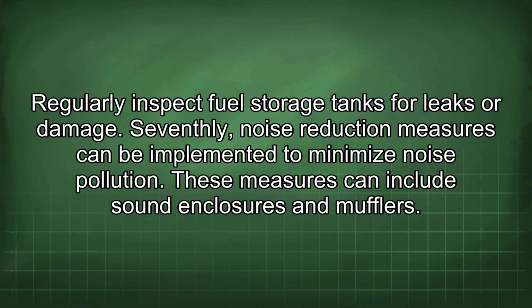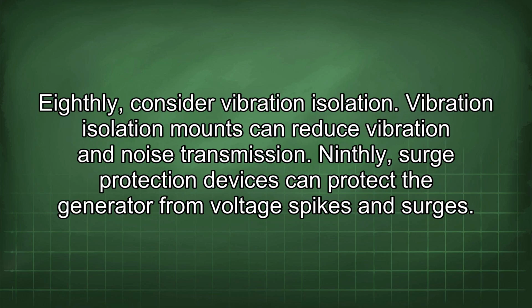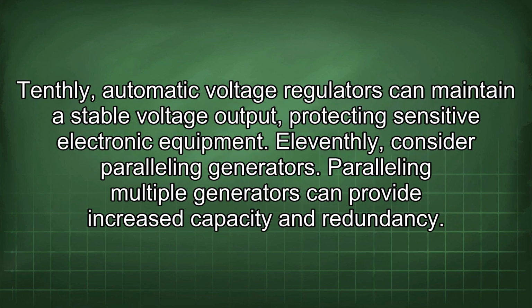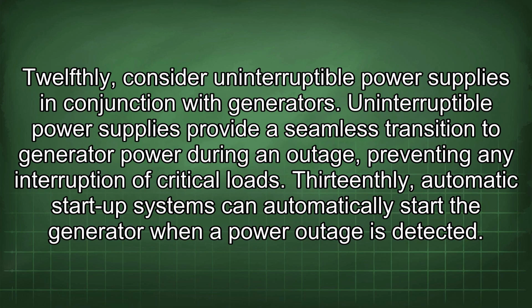Seventhly, noise reduction measures can be implemented to minimize noise pollution. These measures can include sound enclosures and mufflers. Eighthly, consider vibration isolation. Vibration isolation mounts can reduce vibration and noise transmission. Ninthly, surge protection devices can protect the generator from voltage spikes and surges. Tenthly, automatic voltage regulators can maintain a stable voltage output, protecting sensitive electronic equipment. 11thly, consider paralleling generators. Paralleling multiple generators can provide increased capacity and redundancy. 12thly, consider uninterruptible power supplies in conjunction with generators. Uninterruptible power supplies provide a seamless transition to generator power during an outage, preventing any interruption of critical loads.